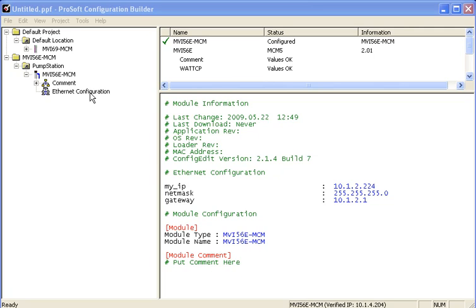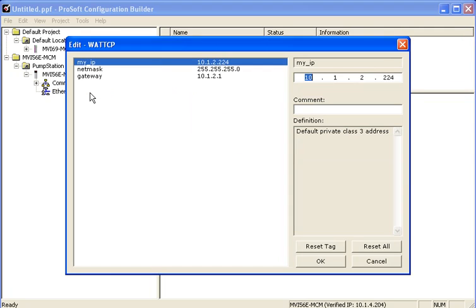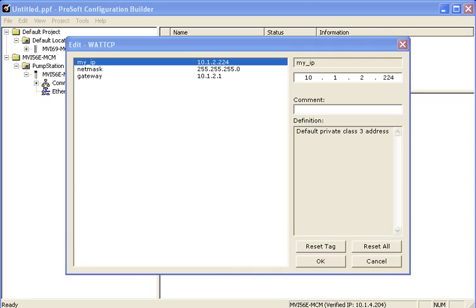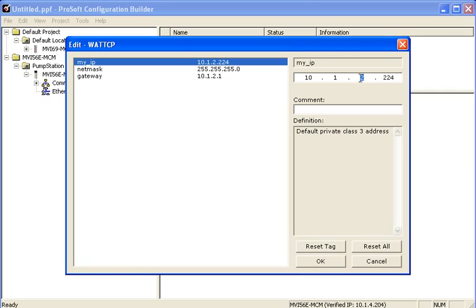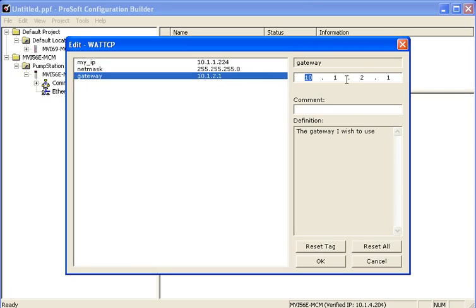I've already showed you how to assign a temporary IP address to the module and now I'll show you how to assign a permanent IP address to the module. From here I'll double click on Ethernet configuration and then you see the WattCP window open. And here you simply modify the My IP, NetMask, and Gateway sections to reflect the IP address, Gateway, and NetMask that you want your unit to use. Once you've done all that, you can go ahead and click the OK button.